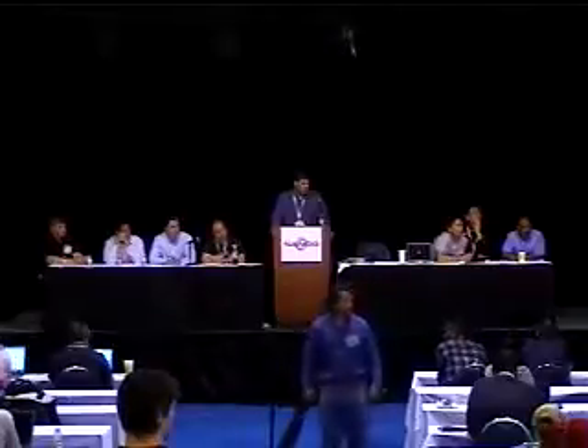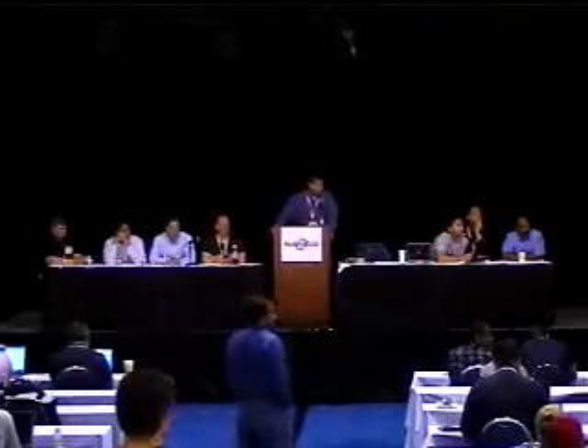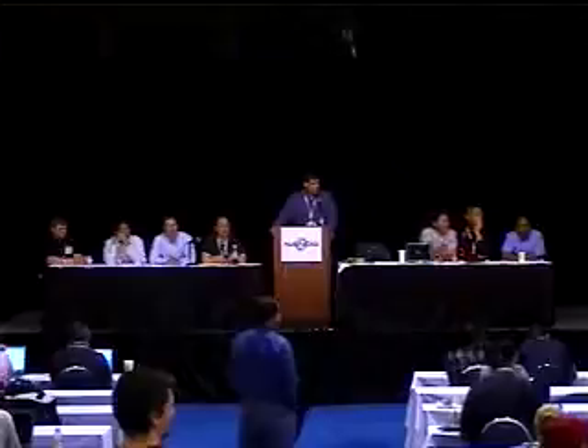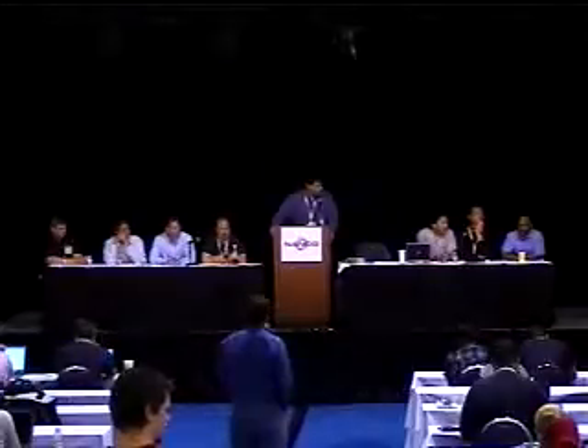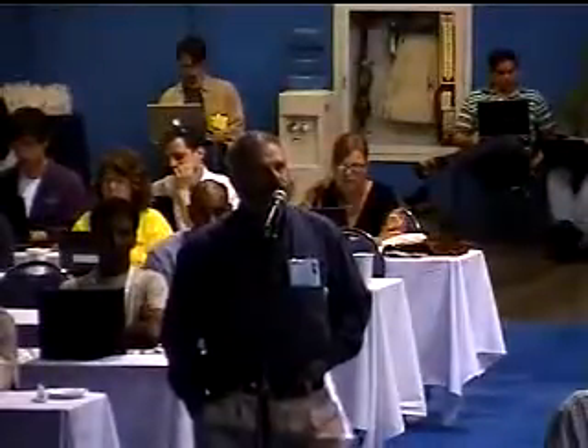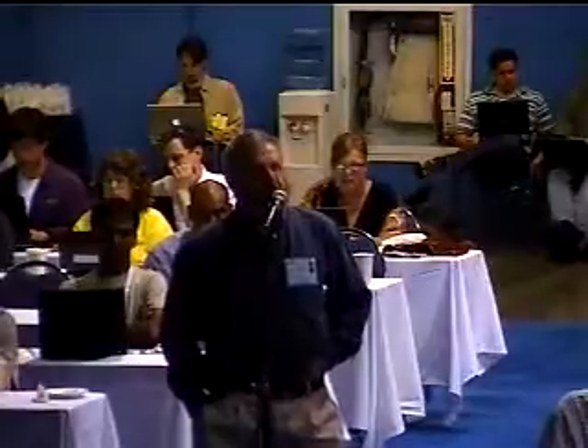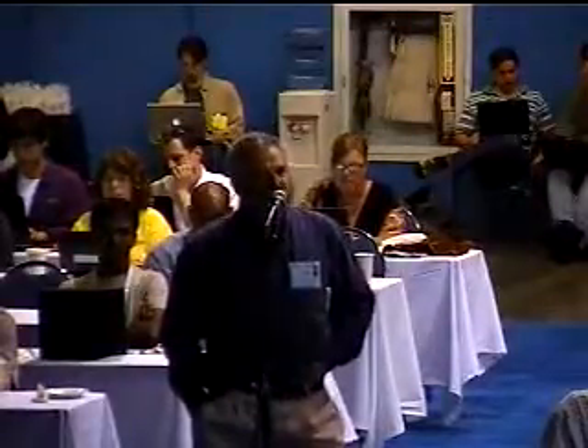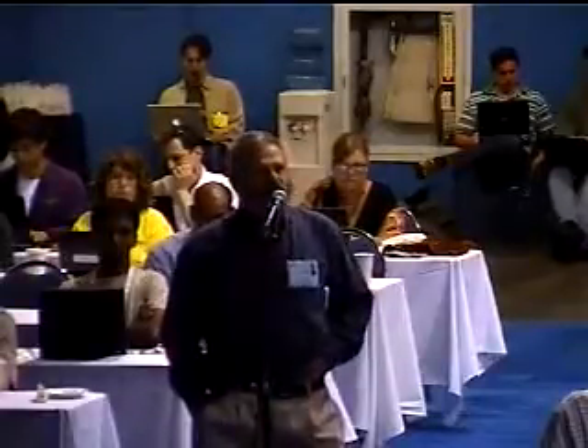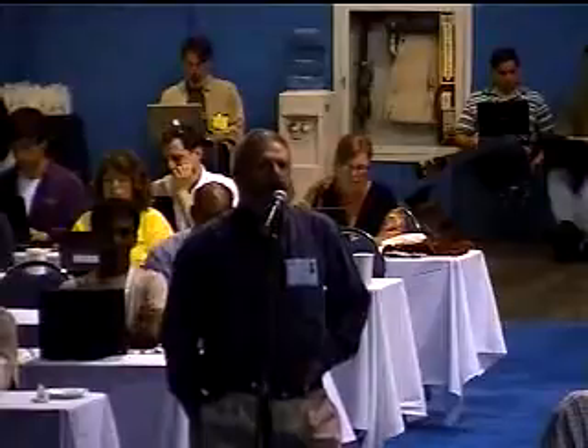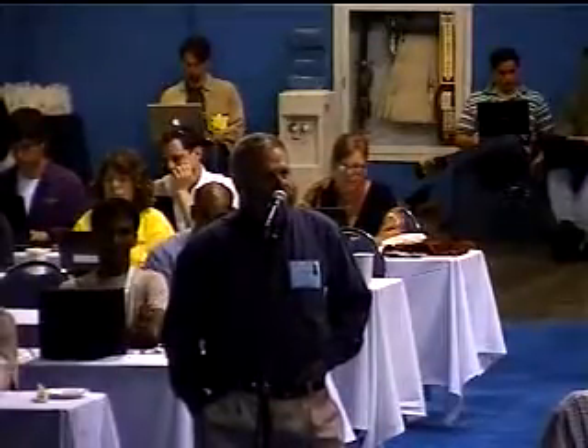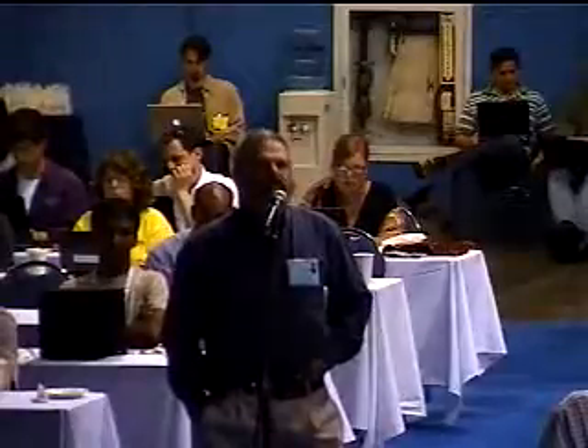Build your facility for 3K per square meter. Cool, give me a half. I'm spaced out too, I'm going to have to pay for it. Give me $500 million and I'll do it. No, your problem raising your capital is somebody putting racks in there. It's my problem to pay for the cost so you can continue to have your rice bowl filled. But the reality is that I'm going to burn as hot as I can because I want to move those stupid little electrons. And I want you to give me a facility that can take as much as you can without blowing me off my feet when I walk into it. And raise the plenum higher and start talking about cooling coming up, air coming up the side of the rack and crossing it.